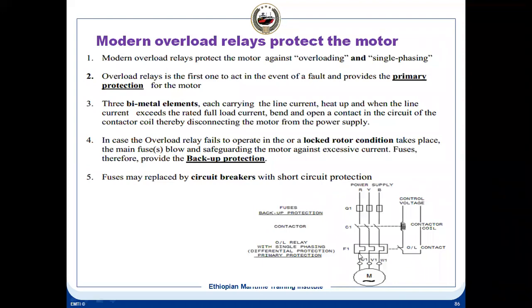So you can see the overload coil here. The main supply for the control, the coil supply, is connected through this overload coil. Whenever the overload coil operates, it opens the supply for the contactor and the motor trips.